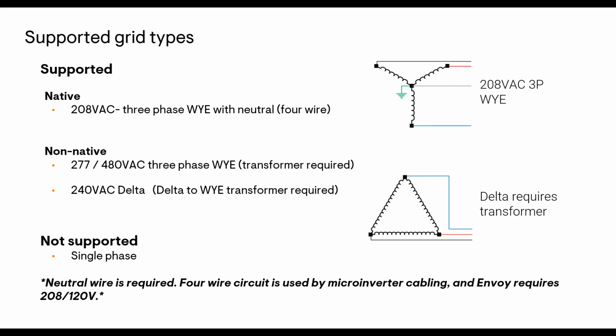The Enphase commercial product that we currently offer does only support native 208 volt 3-phase Y systems. With a transformer, you can support other 3-phase voltages though. So if you're not working with a 208 volt three-phase Y system, you'll have to introduce a transformer in order to use this particular product.